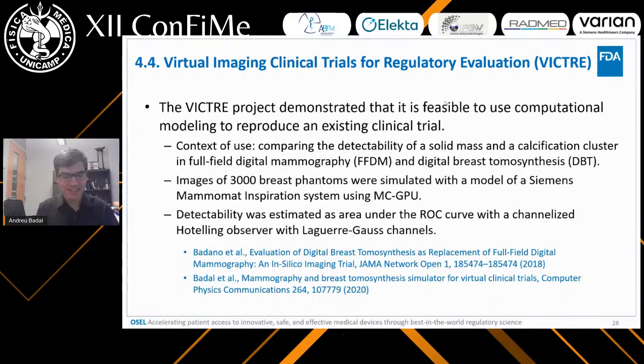Mammography is just like a radiograph of the breast. Tomosynthesis, instead of one radiograph, what this company does is acquire 15 projections over plus minus 25 degrees. So they go 50 degrees in an arc and get all these projections, and then they try to do a 3D reconstruction. It's not the same 3D reconstruction you do with a CT where you have full information around the object. It's a limited view tomography, but it gives you depth information.